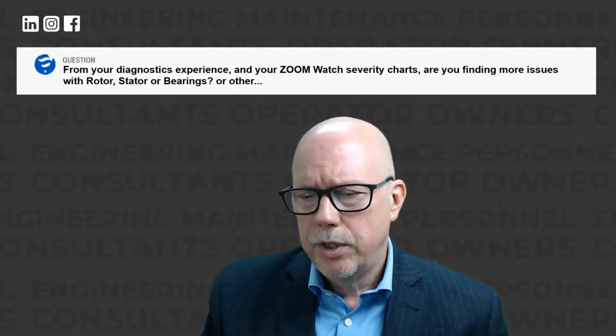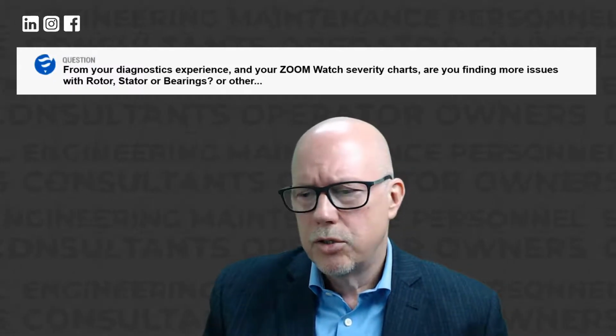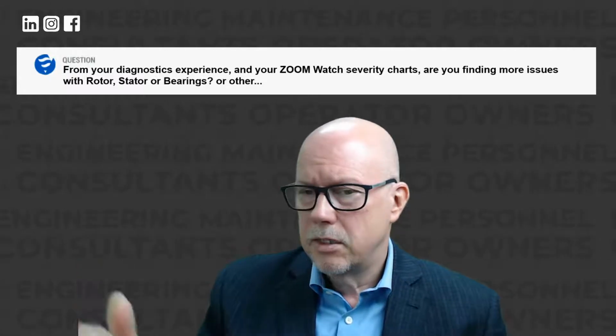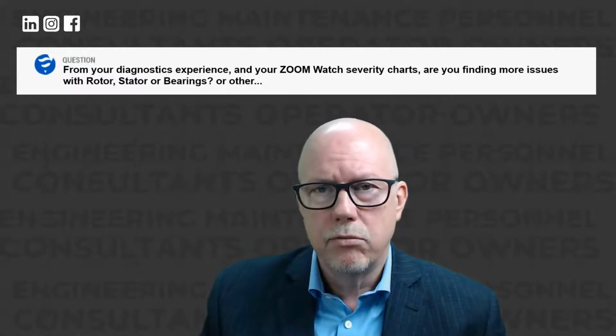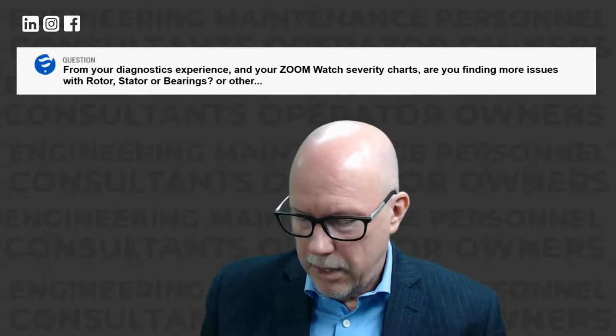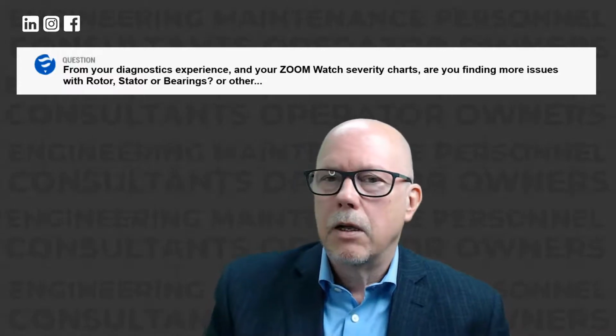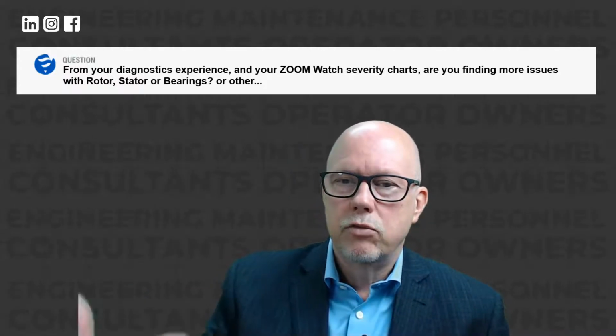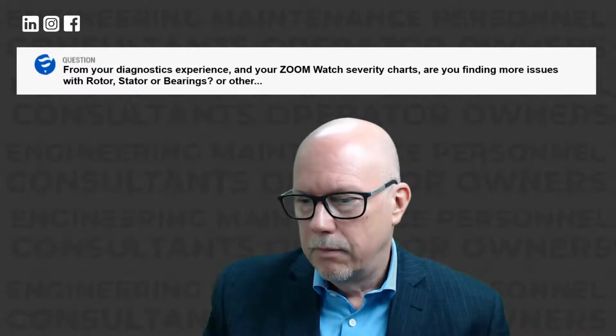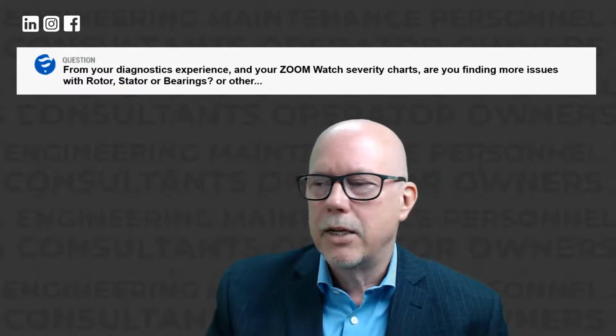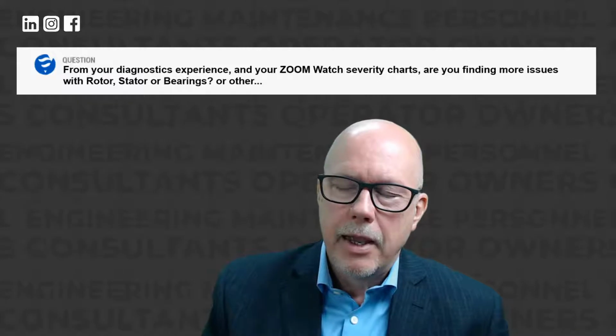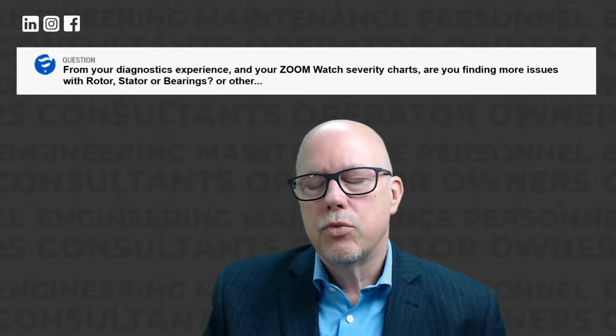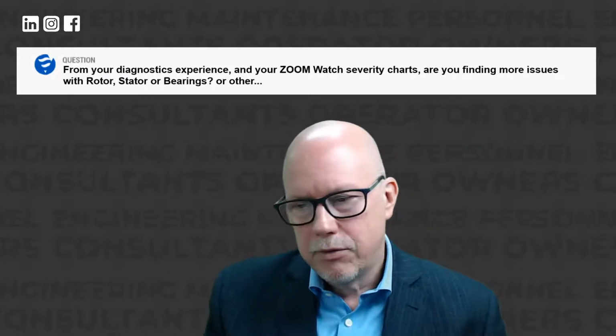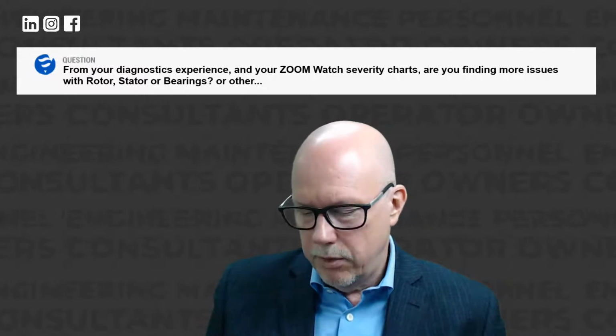But we do see serious issues with the stator too. One famous case in Brazil showed that the stator moved downstream — that raised a lot of eyebrows. When they applied the field, the unit would actually move downstream. That's quite uncommon, though. We also see a lot of issues with bearings, shafts, and misalignments — you do see quite a few of those.